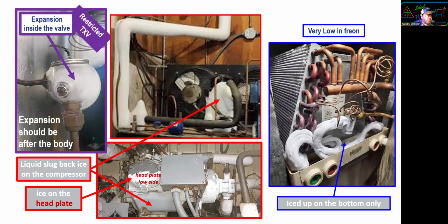Expansion should be after the body. Alrighty. On the red, liquid slug on the compressor. This is slugging in the middle. The one of the blue is slugging, because the bottom picture, if you remember a compressor, the head is not supposed to be iced. In freezers we can have the whole body iced up. It's fine as long as there's no ice on the head. If you see ice on the head, that means we have liquid slug back.